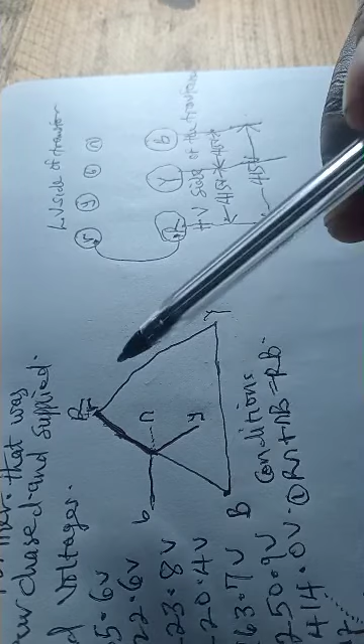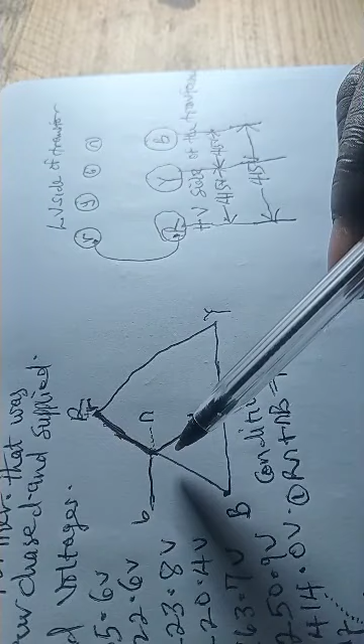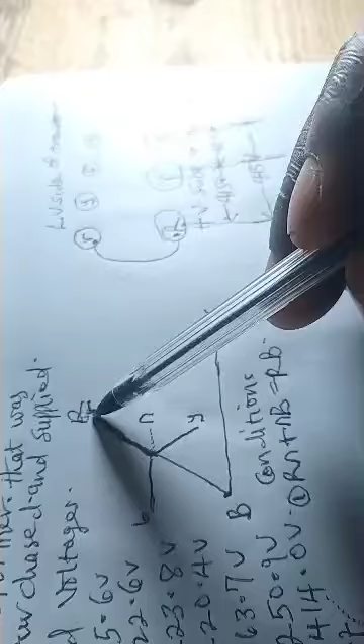Meaning that the applied voltage red, yellow, blue that you applied, you have connected your small low voltage red bushing to the high voltage red bushing. Now you measure voltage between the red bushing to the neutral of the LV. You record the number. You measure voltage between neutral and blue phase of the bushing, high voltage side. You record it. Then you now measure across blue and red. You record the same value. All this I'm explaining, you'll see it from our readings now.